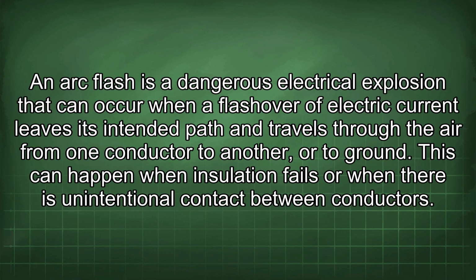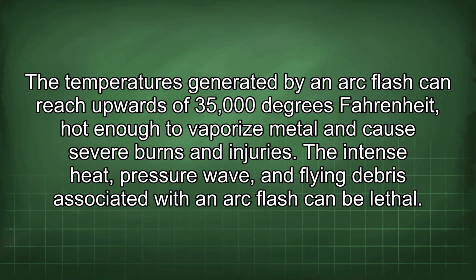An arc flash is a dangerous electrical explosion that can occur when a flashover of electric current leaves its intended path and travels through the air from one conductor to another, or to ground. This can happen when insulation fails or when there is unintentional contact between conductors. The temperatures generated by an arc flash can reach upwards of 35,000 degrees Fahrenheit, hot enough to vaporize metal and cause severe burns and injuries. The intense heat, pressure wave, and flying debris associated with an arc flash can be lethal.